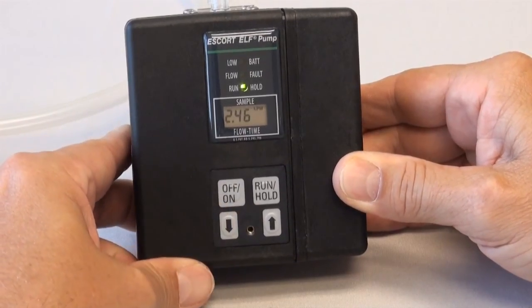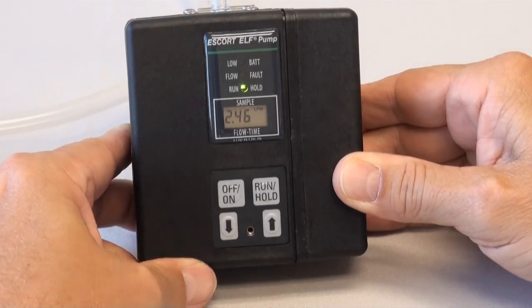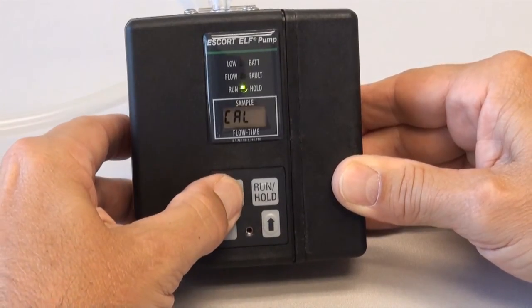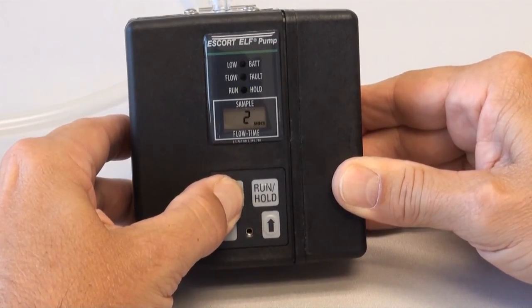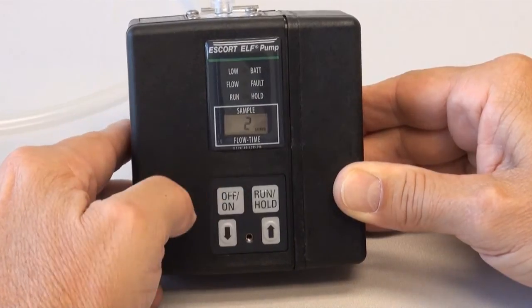The Escort Elf is now calibrated. Because the Escort Elf has an internal secondary calibration, the pump will only need to be calibrated to a primary standard once a month. Or, for coal mine dust sampling, MSHA requires recalibration every 200 hours.